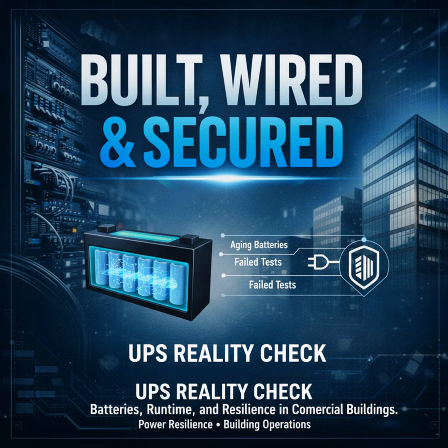You mentioned testing. Too many teams rely on quick vendor-run tests. How should testing be done instead? Test with realistic loads and duration. If tenants expect 10 minutes of runtime, test for 10 minutes at representative load, not at 20% load for 30 seconds. Include battery discharge tests under actual environmental conditions, and log voltage, current, and temperature so you see performance trends.